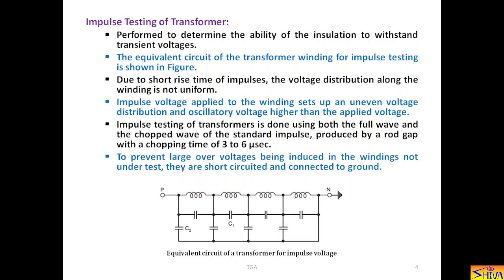So, after chopping, whatever voltage is coming that is necessary to measure or it is necessary to test the insulation by that type of voltage wave. Hence, chopped voltage wave of standard impulse is applied. And this chopping is done by using a rod gap. Chopping time is 3 to 6 microseconds.